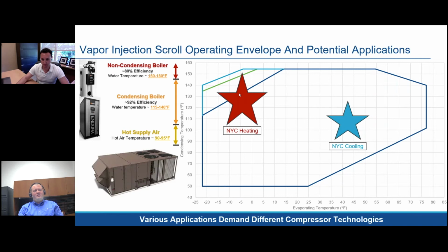Generally, I don't know if you can see the colors very well, but if you're inside this purple envelope right here, typically you don't need vapor injection. You won't get the extra capacity for heating, but you just won't need it. You start getting into vapor injection between this purple and green area, then you start getting into wet and liquid injection requirements as you go above that green area. This is just a more generic envelope. Envelopes are specific to the specific compressor, but typically, the higher the compression ratio you go, the more you start needing vapor injection, and then wet injection, which is a vapor and liquid mix.